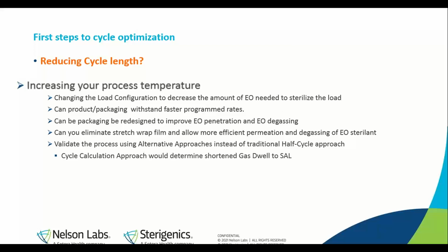If I see today that the temperature of your process is not as high as I would like, I would always encourage you to look at increasing the temperature of the process. As you increase the temperature of the process, you have a chance to improve the effectiveness of the ethylene oxide molecule, not just for sterilization, but for degassing. So consider looking at that.